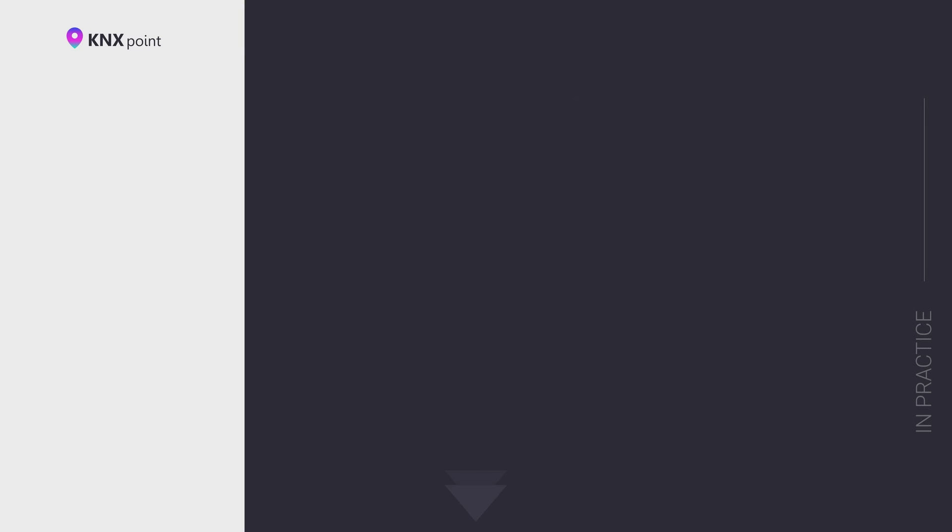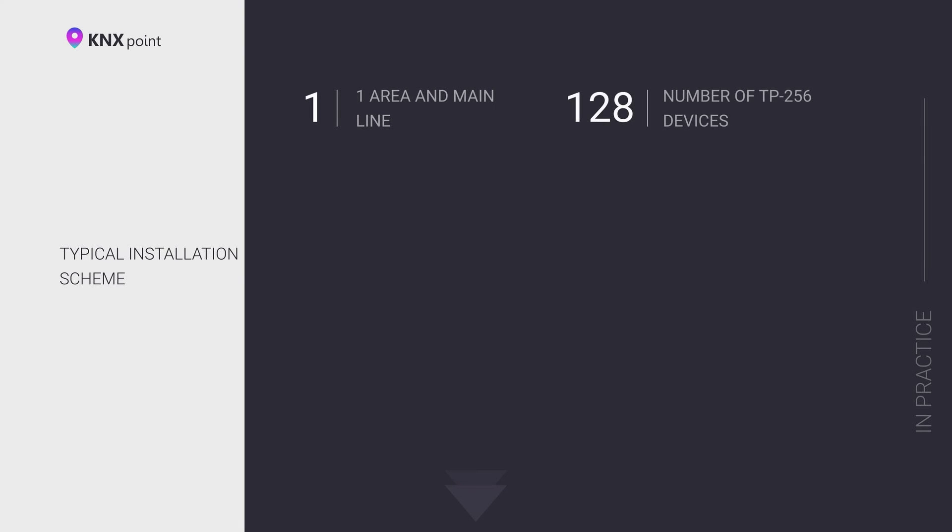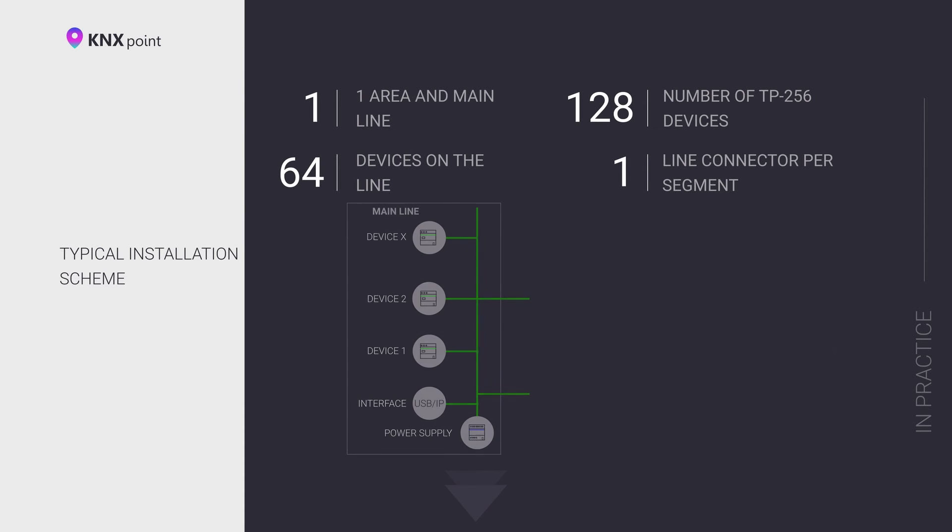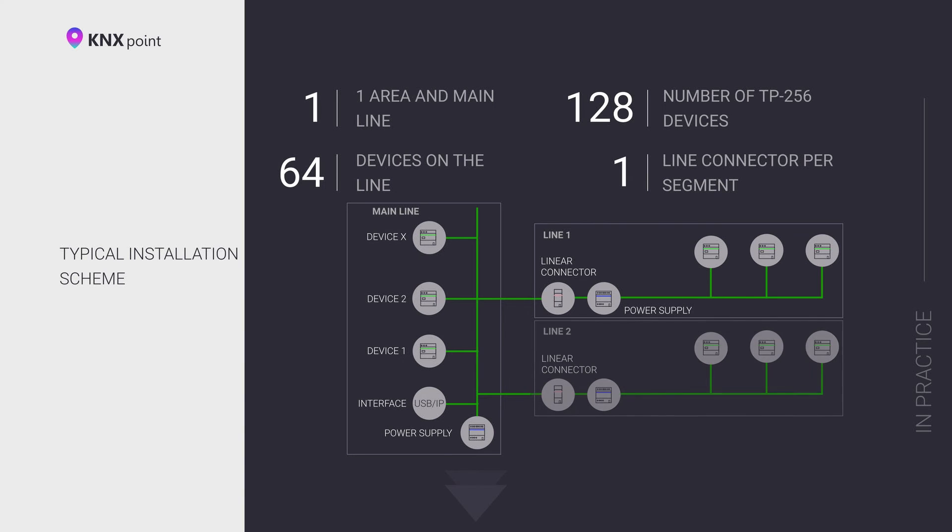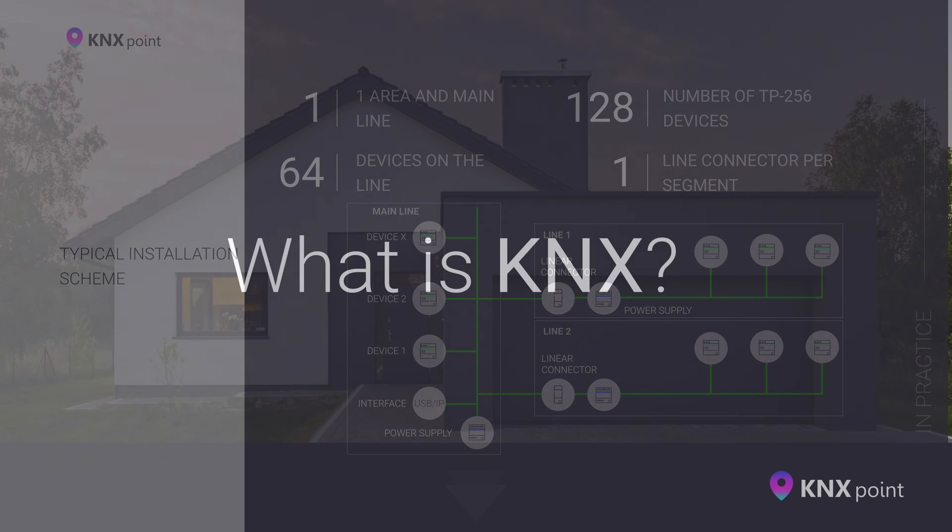Let's take a look at the topology of a typical installation layout. Important system devices are located on the main line. Additional lines can be connected to the main line using line connectors. Usually, additional lines are separate floors of a building with switches and floor control panels. We recommend using IP gateways to connect lines when scaling the system for very large facilities. Among other things, IP gateways serve as a link between KNX and dispatch system.